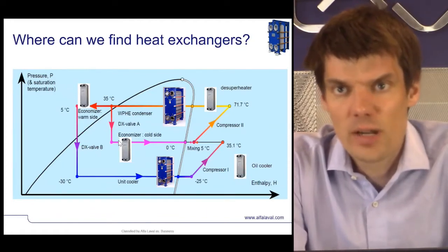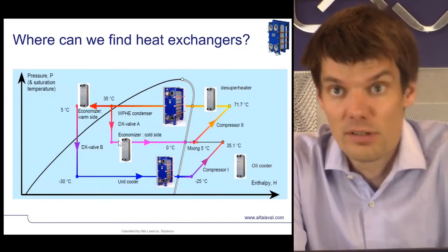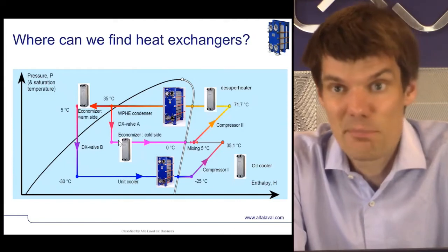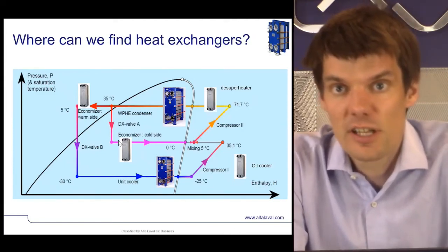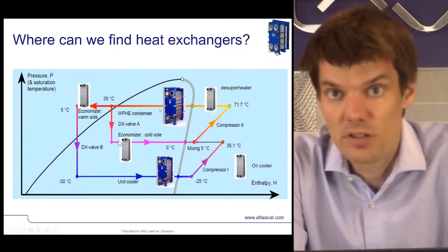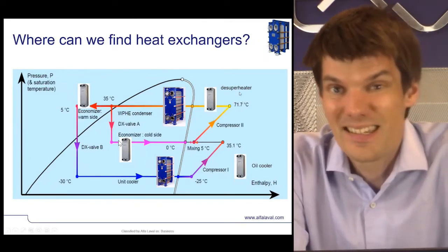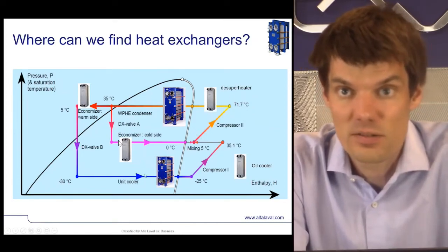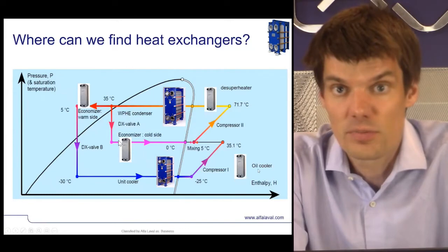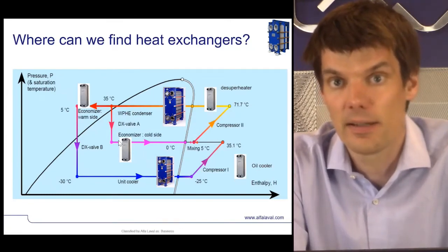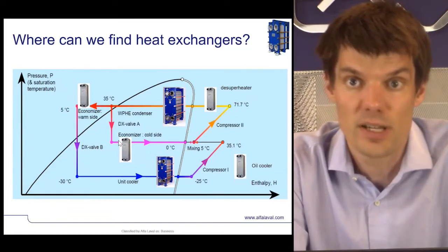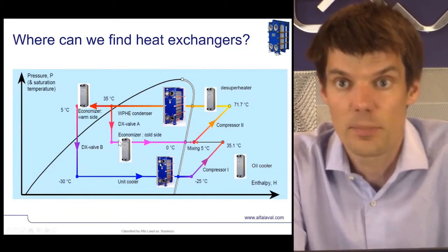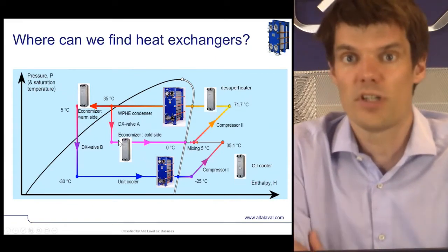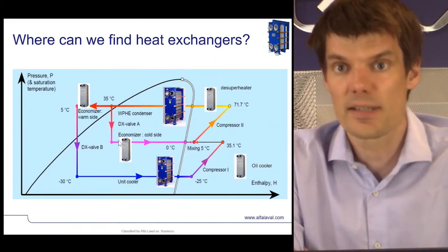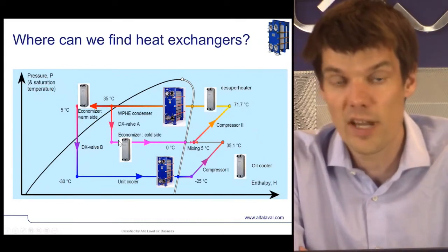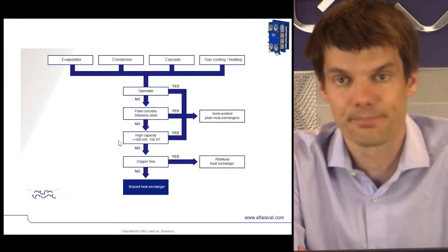So the first question here is, where will I find a heat exchanger in a refrigeration system? Well, the answer is approximately all over the place. Traditionally, we will have plate heat exchangers as evaporators and condensers, but we can also find them as DX superheaters, subcoolers, economizers, and not least as compressor oil coolers. Depending on the system size and the refrigerant used, these heat exchangers can be of brazed or fusion bonded design, or even semi-welded types. But before we look more deeply into each of these technologies, let's spend a minute on seeing where to use which type of heat exchanger.